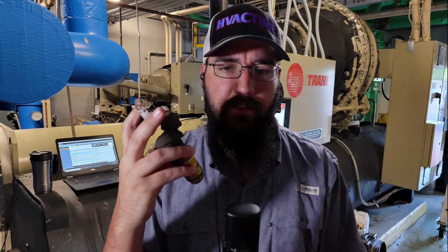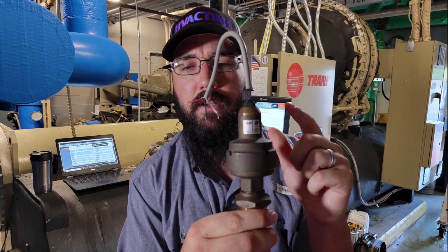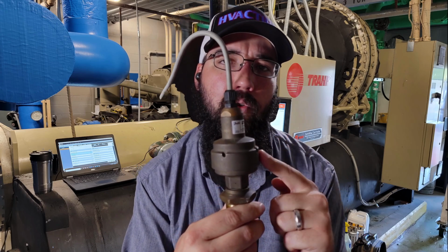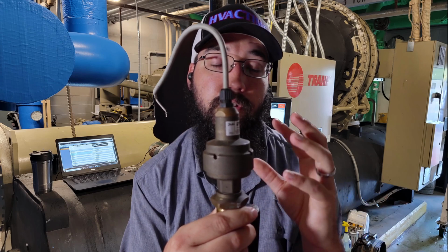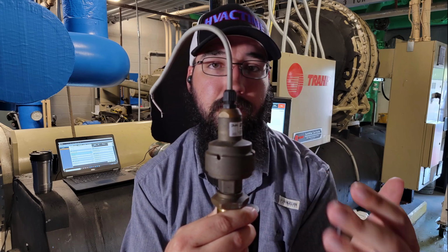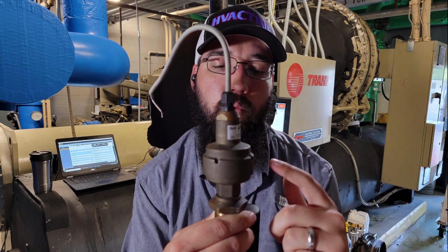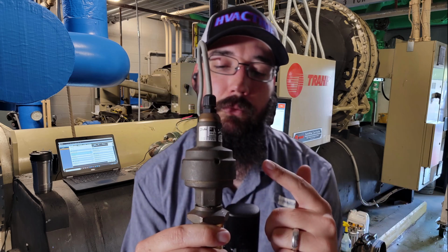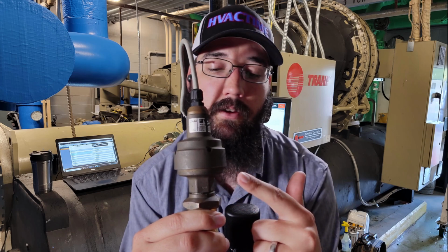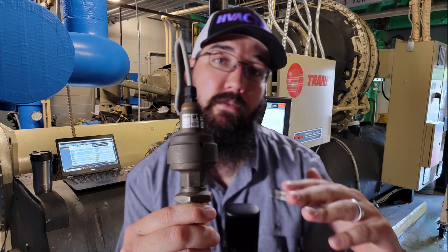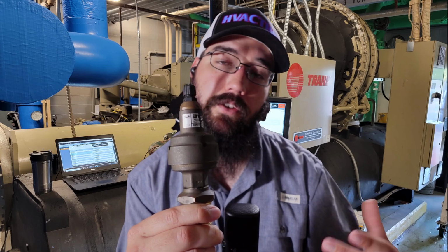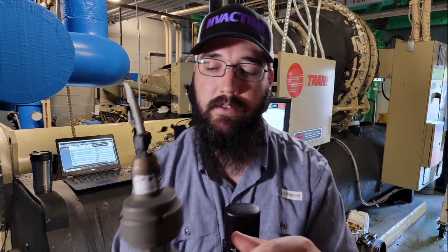Now, one of the other things that you need to be mindful of, if you do a repair and replace one of these valve heads, is making sure that the polarity is correct. I've had it to where the polarity changed from an older style to the newer style, or even just from valve to valve. Sometimes it's an exact like for like swap, they're identical, but one rotates in a different polarity. So when we're doing a calibration upon replacement, make sure that you're actually paying attention, and when it's supposed to close, it actually closes. And that's again where the sight glass comes in. You can see that process happen.